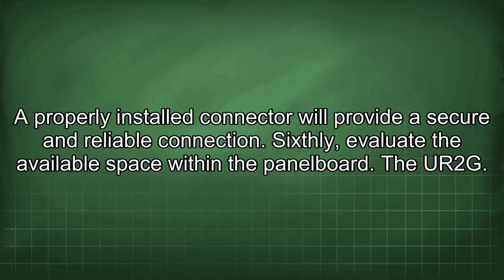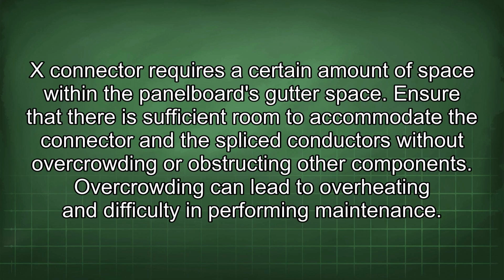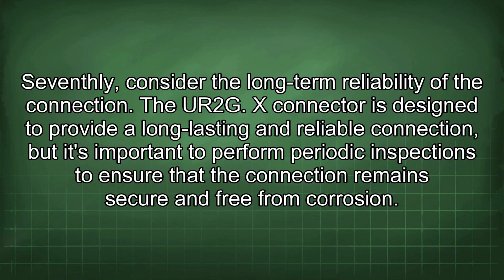Sixthly, evaluate the available space within the panel board. The UR2G X connector requires a certain amount of space within the panel board's gutter space. Ensure that there is sufficient room to accommodate the connector and the splice conductors without overcrowding or obstructing other components. Overcrowding can lead to overheating and difficulty in performing maintenance. Seventhly, consider the long-term reliability of the connection. The UR2G X connector is designed to provide a long-lasting and reliable connection, but it's important to perform periodic inspections to ensure that the connection remains secure and free from corrosion.